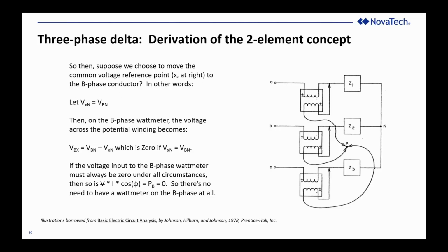So if X, the common reference point for all 3 voltages, doesn't have to be on the neutral, then we can make that Vx to neutral any value we want. Why don't we make it the B-phase conductor? If we make it the B-phase conductor, a couple of things happen. So number one, the B-phase wattmeter is measuring the voltage from the B-phase conductor to the B-phase conductor, which is 0. And 0 volts times any amount of current is 0 watts. So the B-phase wattmeter will always read 0 as long as there's no neutral current.